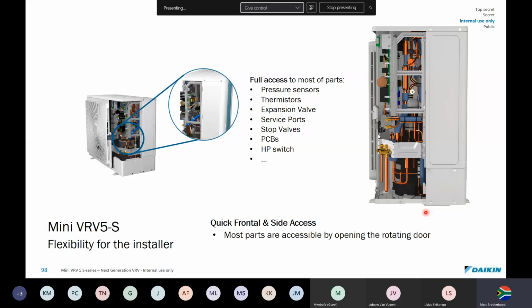Because of this, they've also made easier access. They had a lot of complaints with the previous VRVs. So there's full access to most parts: pressure sensors, thermistors, expansion valves, easy to get to now. You don't need to strip off the machine. Circuit boards, fairly easy, your high pressure switch. So nearly everything's available just by taking out one screw, and then the door hinges and it unclips.